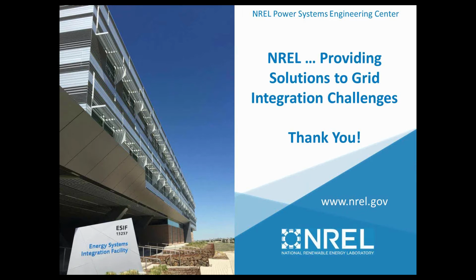Okay. Next one. Considering the footnote in 1547, islanding risk can be ignored if a test was conducted. Does this apply when you have multiple type inverters in a potential island where all of the individual equipment was tested to UL? So UL 1741 and IEEE 1547.1 replicate basically the same test. My opinion on reading the footnote would be that if you have a singular system and it passes the test, then that should be considered anti-islanding or non-islanding inverter.